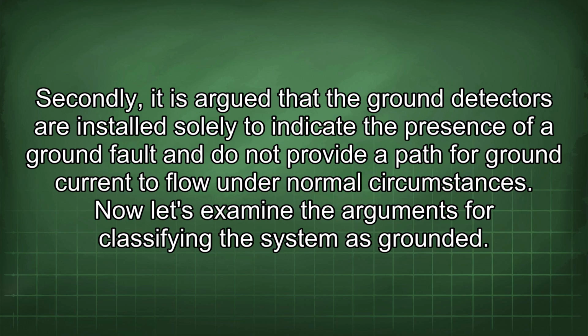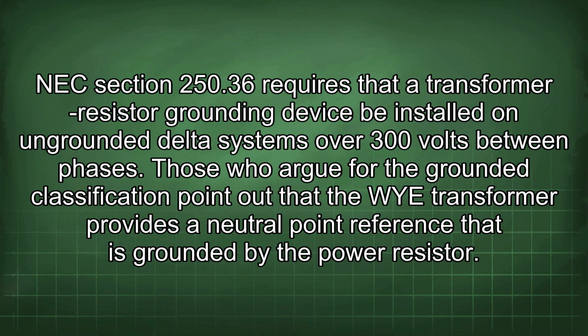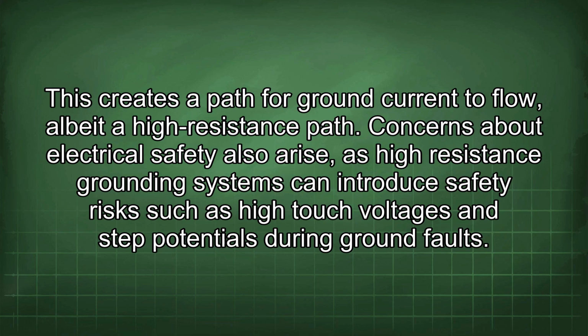Now let's examine the arguments for classifying the system as grounded. NEC section 250.36 requires that a transformer resistor grounding device be installed on ungrounded delta systems over 300 volts between phases. Those who argue for the grounded classification point out that the WYE transformer provides a neutral point reference that is grounded by the power resistor. This creates a path for ground current to flow, albeit a high resistance path. Concerns about electrical safety also arise, as high resistance grounding systems can introduce safety risks such as high touch voltages and step potentials during ground faults.